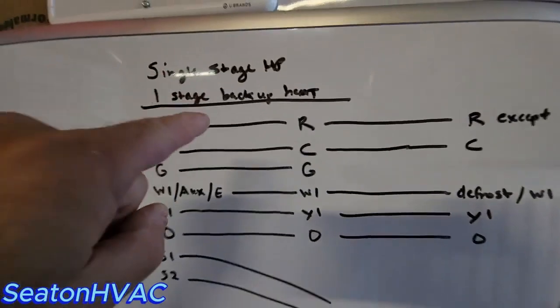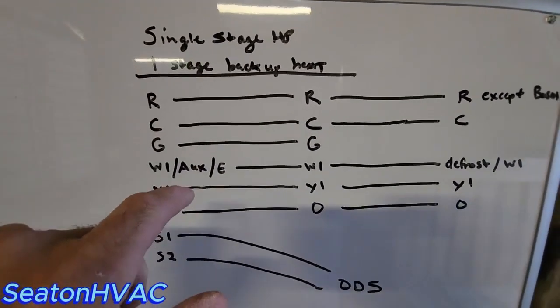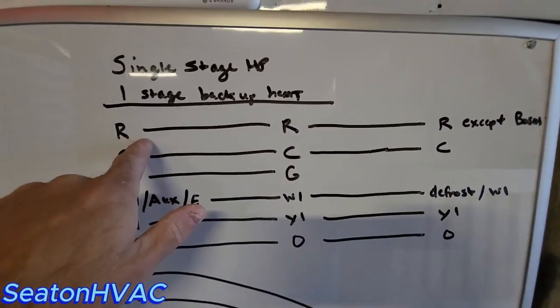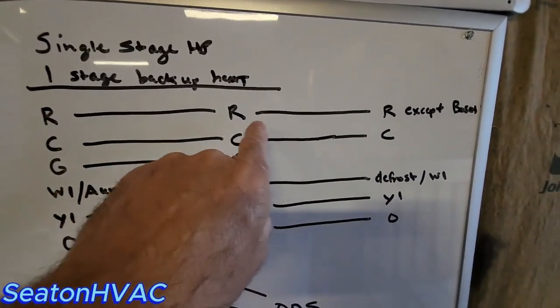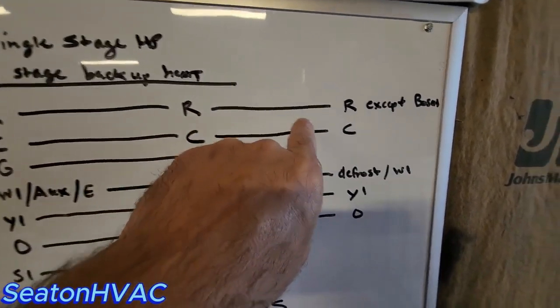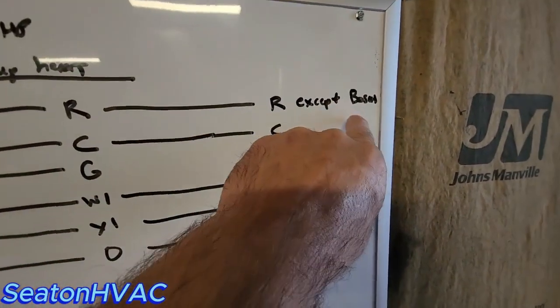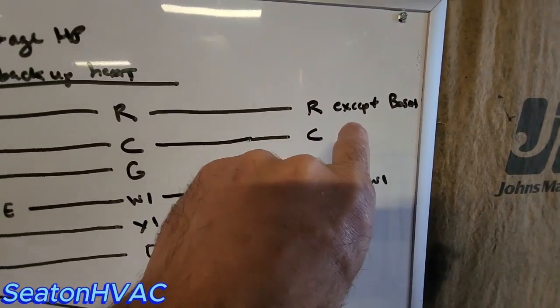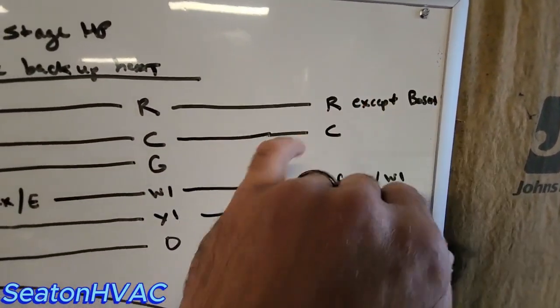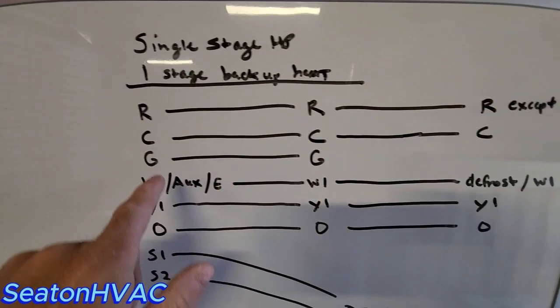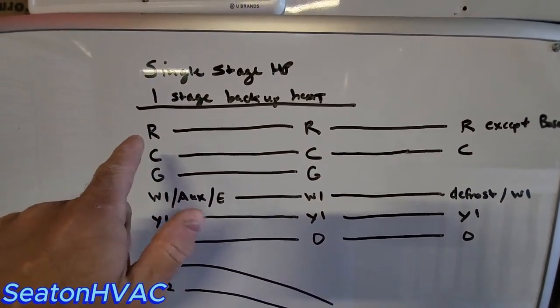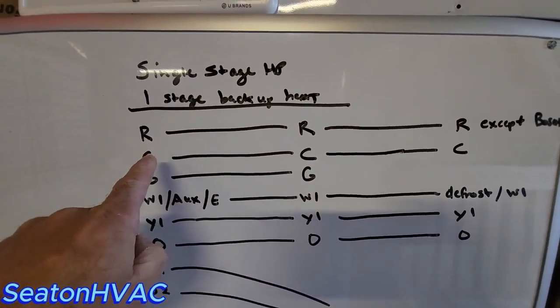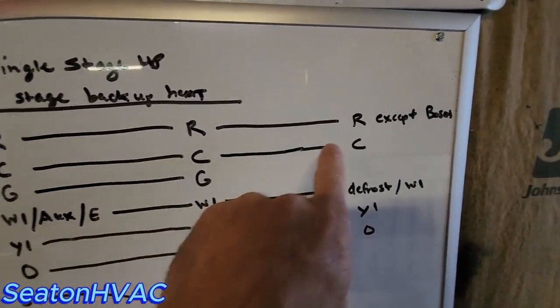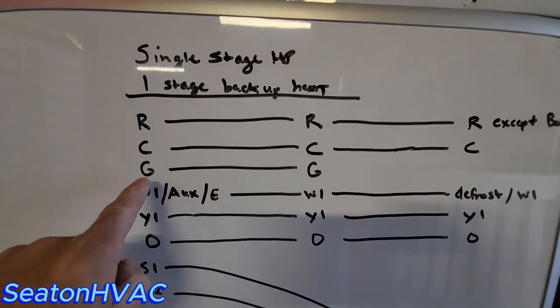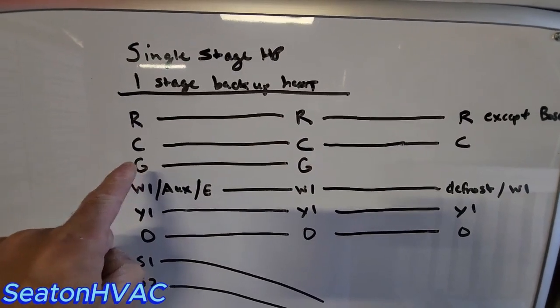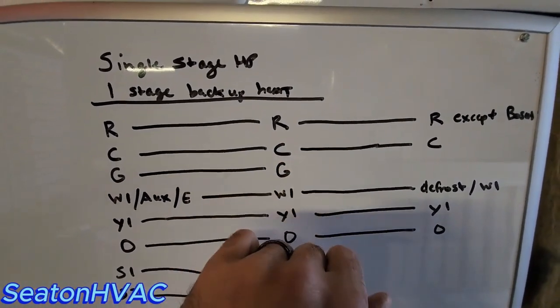Okay, guys, single-stage heat pump with one stage of backup heat. Pretty similar to gas furnaces and ACs, but a little bit different. So you got R from your thermostat to your air handling unit. Then R goes outside, except for the Bosch units that don't have an R that goes outside. But most heat pumps, standard heat pumps, are going to have your red wire that needs to go outside. Your blue wire, your common, same as AC, goes from your thermostat to your air handling unit to your heat pump. G just goes from your thermostat to your air handler because it's just going to control the indoor fan.